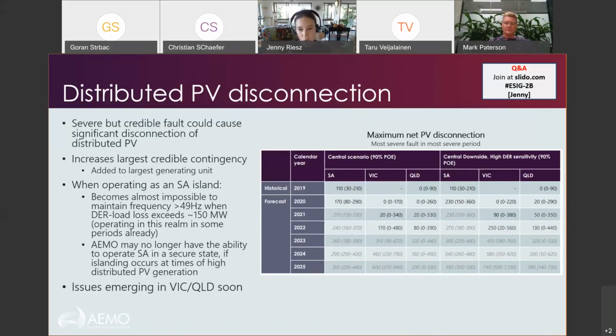So the table here is showing you the net disconnection of PV that we expect, or that we've projected based upon these models, in South Australia, Victoria and Queensland under two scenarios. The left columns are the central scenario from the ESOO, and the right-hand columns are a sensitivity around that where we've got more PV and a bit less load. So it's a more extreme case. You can see that in South Australia, even in historical periods, we're looking at very large amounts of PV tripping off, around 100 megawatts or more. And the values in brackets give you the range of uncertainty. There is some uncertainty around this.